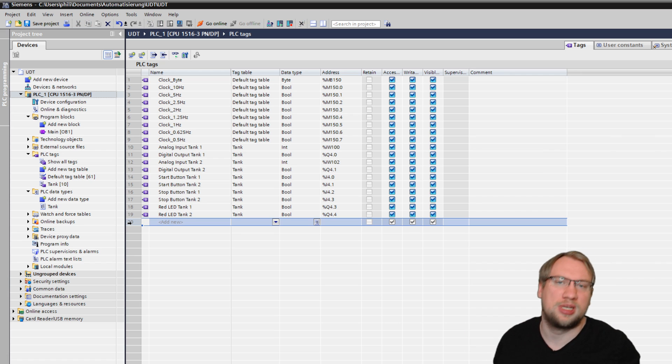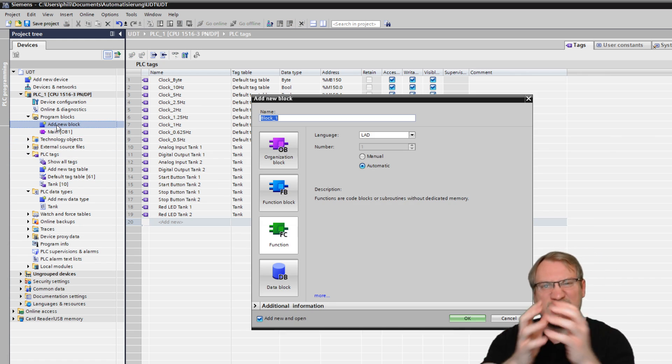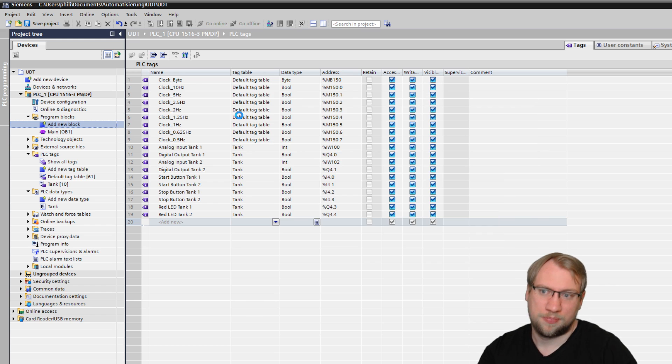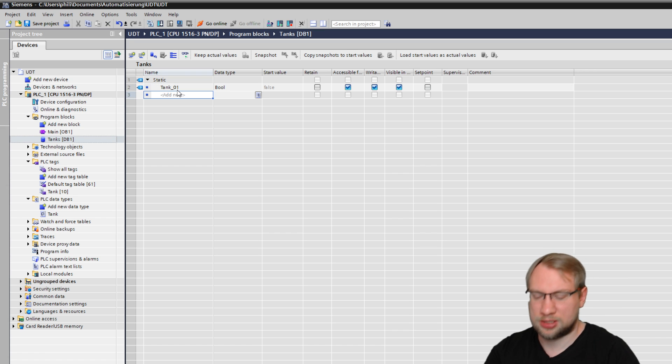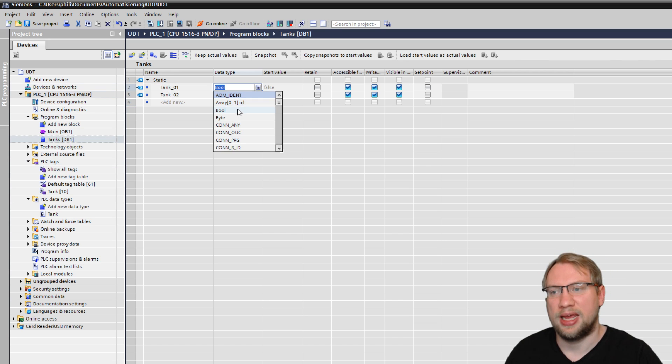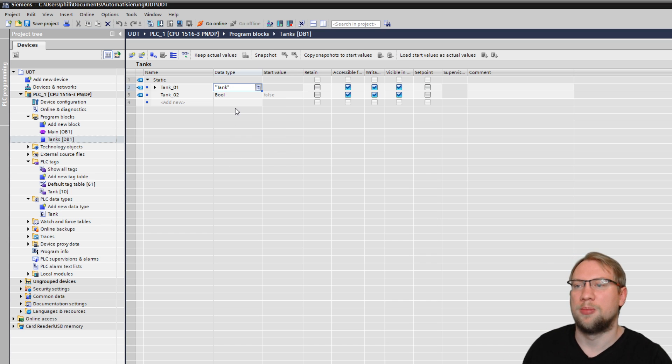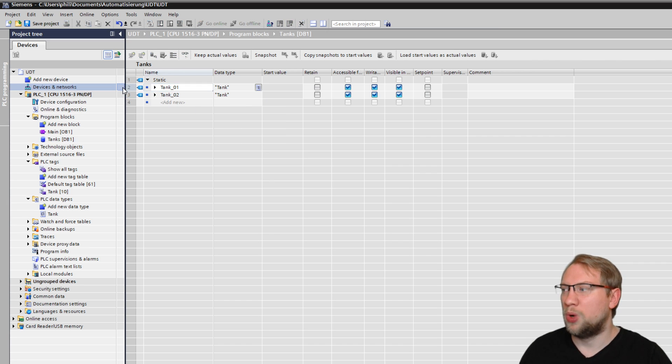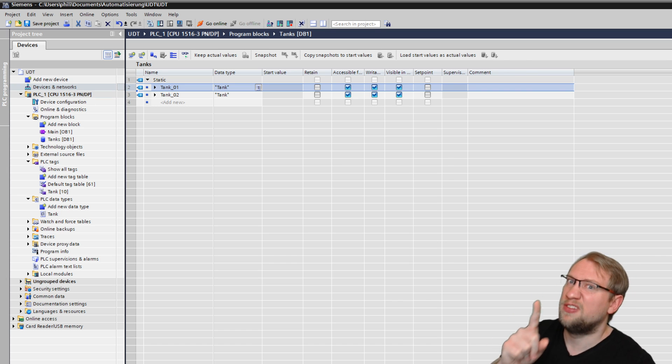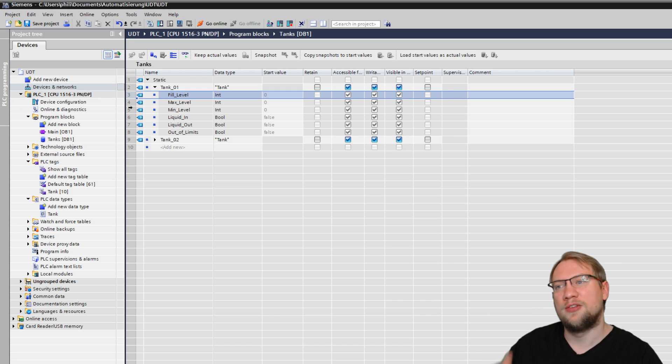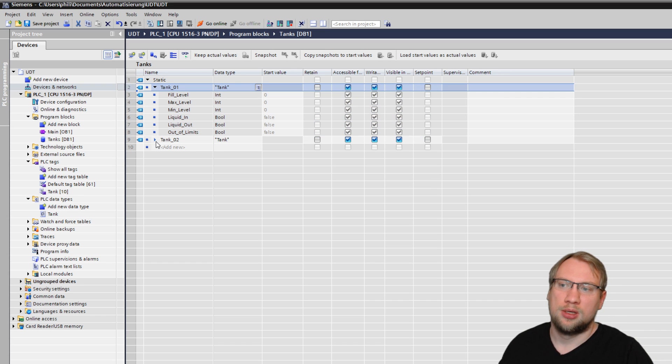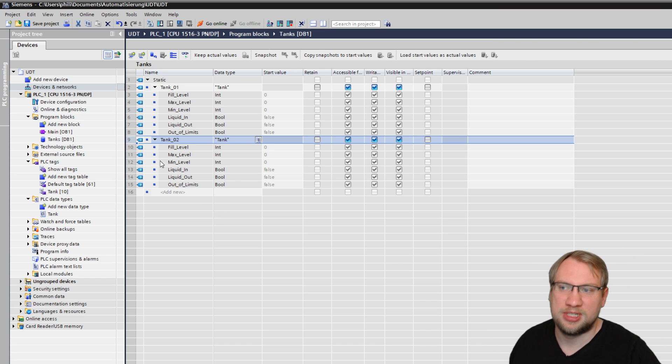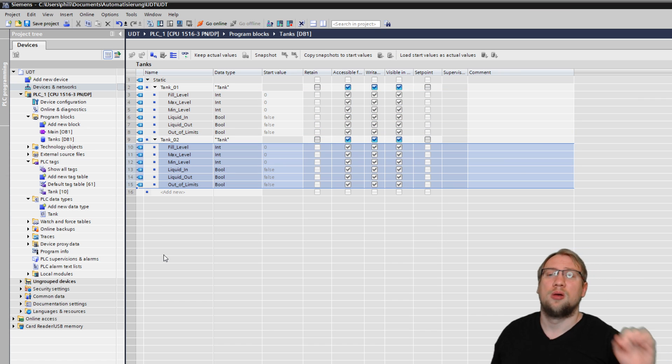So I have a fill level. I have a maximum level, minimum level, liquid out, and so on, and so on. This is right now not perfect to do it in the tag table. Of course, depending on the case that you have. That's why I delete it. And I will make a new block. I want my tank data to be stored in data blocks. So I will create a data block. This I will call tanks. And there I can just say tank01, and tank02. And those two, they are both of type, make a guess, tank. Usually it's at the bottom or at the top. Tank and tank. And now you can see, this is just one line, meaning it's just one variable, because that's what it is. It is just one variable. But this variable has some subtypes. It has one integer, which indicates the fill level, one maximum level, one minimum. You see, all of these belong to tank1. All of these belong to tank2.